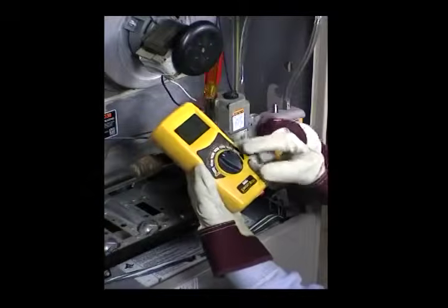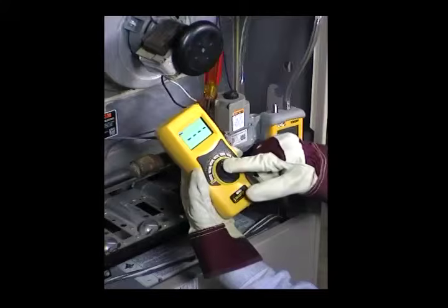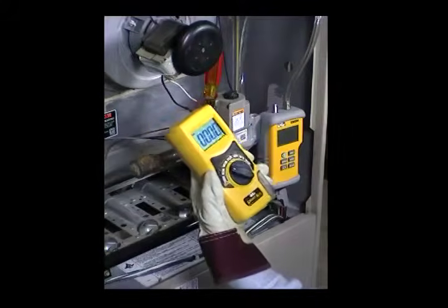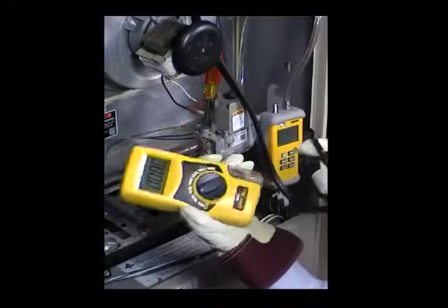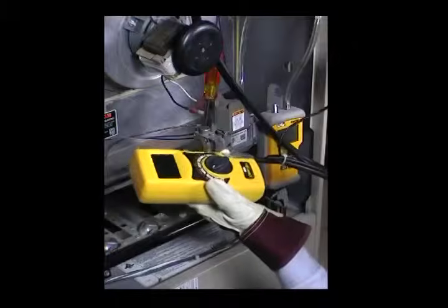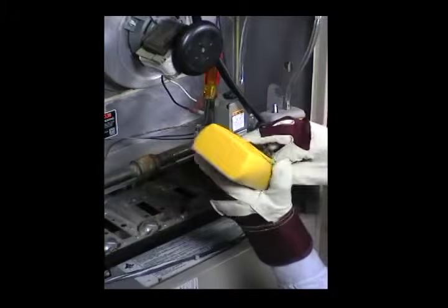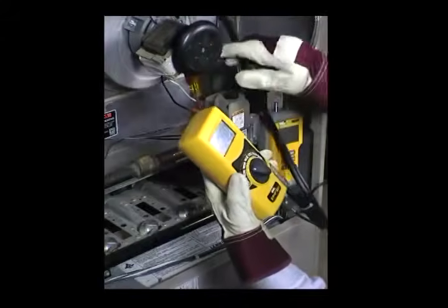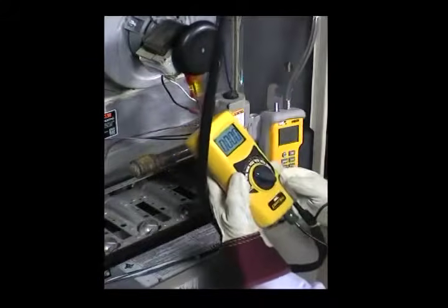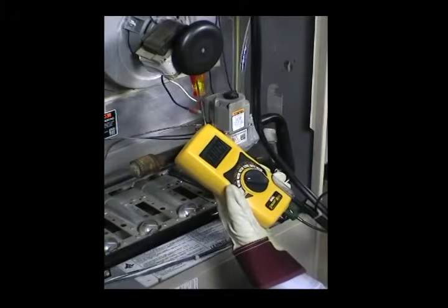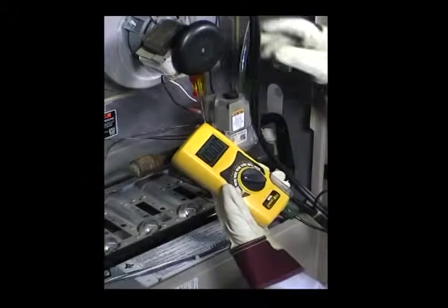So after it goes through 0, you'll see I have dashes and a parameter that's calculated. So I'm just going to go to CO2. I'm going to hook up the flue probe, and I have the flue gases, and then I also have the temperature portion of it, and then I'm going to call for heat. And we've got ignition.